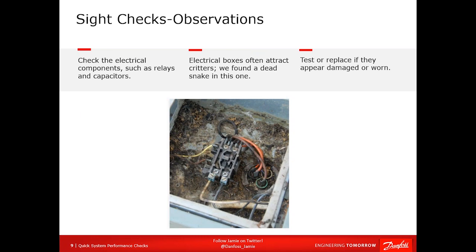Electrical connections — one example here happened to have a snake in it, which scared the technician, but that's not the important part. The main thing is these components were looking pretty tough. The recommendation was to replace them. The conductors were overheated and discolored. All this should be replaced and inspected. If you're replacing an expensive component like a compressor — a couple of grand — it's cheap insurance to make sure this stuff is done, especially the capacitor. A weak capacitor leads to high energy use. If it's a start capacitor and there's a delay on start, you can kiss the life expectancy of the compressor goodbye — you're drawing six times the normal amps for way longer than you should.